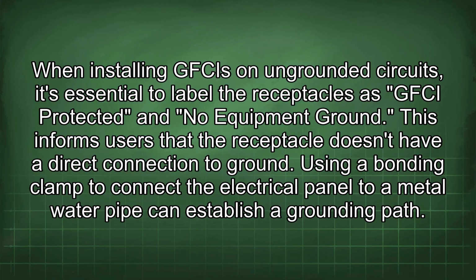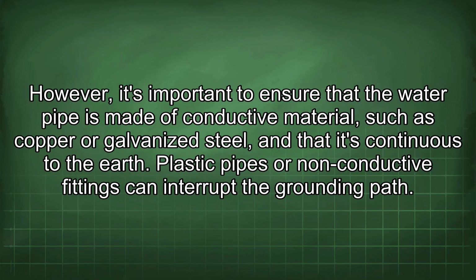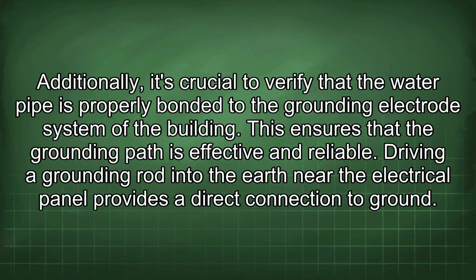Using a bonding clamp to connect the electrical panel to a metal water pipe can establish a grounding path. However, it's important to ensure that the water pipe is made of conductive material, such as copper or galvanized steel, and that it's continuous to the earth. Plastic pipes or non-conductive fittings can interrupt the grounding path. Additionally, it's crucial to verify that the water pipe is properly bonded to the grounding electrode system of the building. This ensures that the grounding path is effective and reliable.